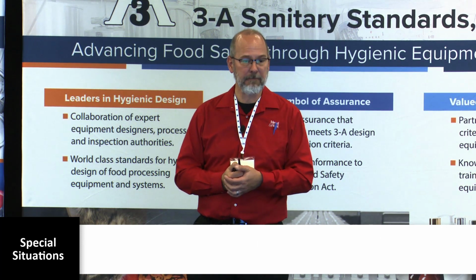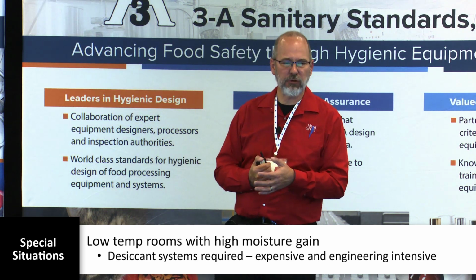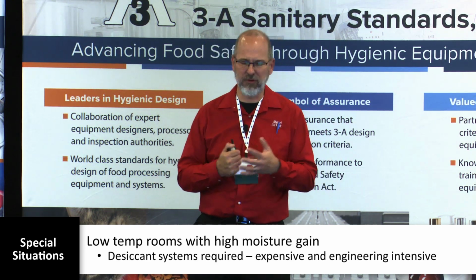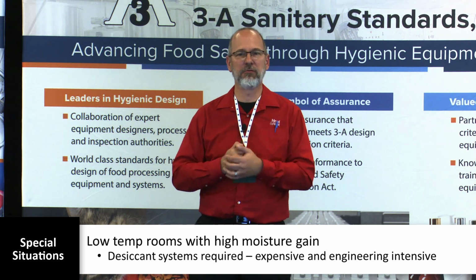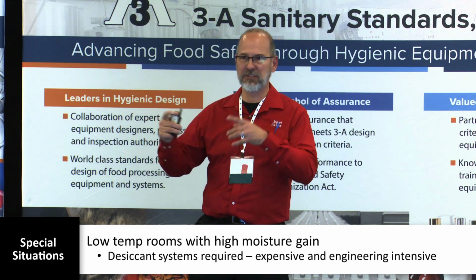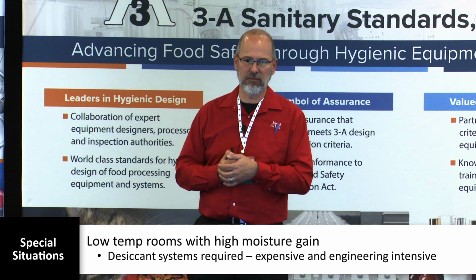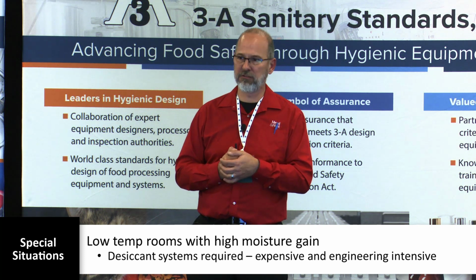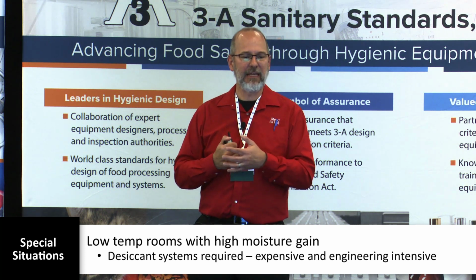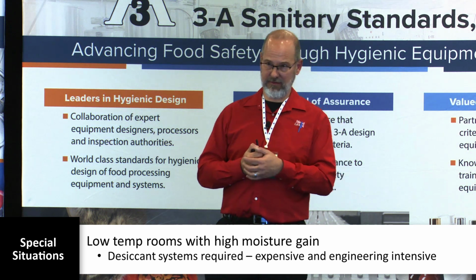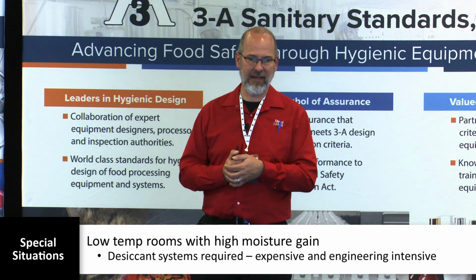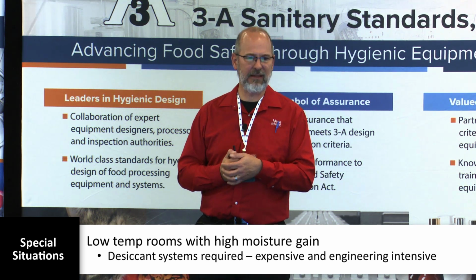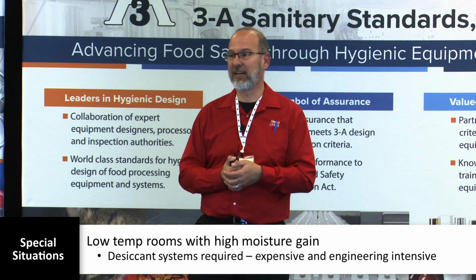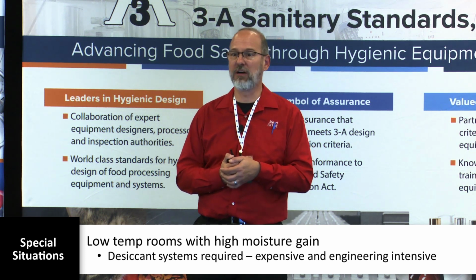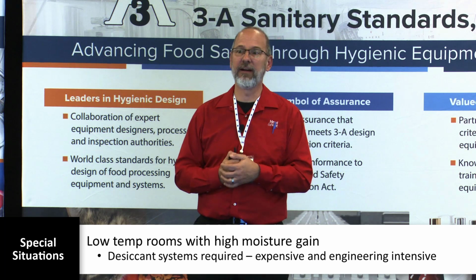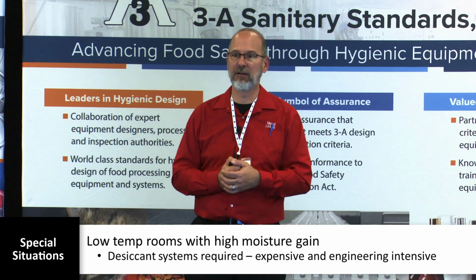Low temperature rooms are kind of a special situation. We've had clients who say, hey, we want to keep our room at 45, 50 degrees, and we've got condensation problems because we've got a lot of cold surface equipment in the room and high humidity. A lot of times you have to look at a desiccant air handling system. And a lot of our clients have had sticker shock when they see what that costs. They're not cheap. They're about twice the cost of a regular food grade air handler, in the neighborhood of $500,000 and up per unit.